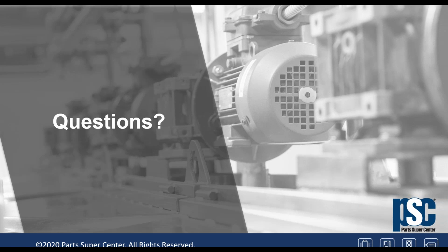And again, the change in power factor and capacitance tells us something is happening to that insulation. Now, we have type U bushings in the field that have been there for 50 years. I don't want to be partial to GE, but I'm waiting to see if the type O plus C lasts 50 years in the field. The best thing to do is test the bushing, which is a pain in the neck because the transformer is energized. Nobody wants to do that.